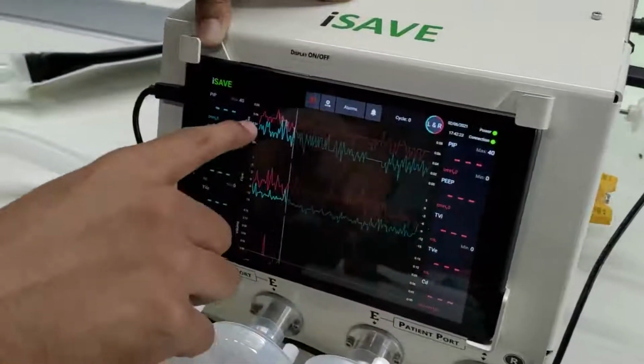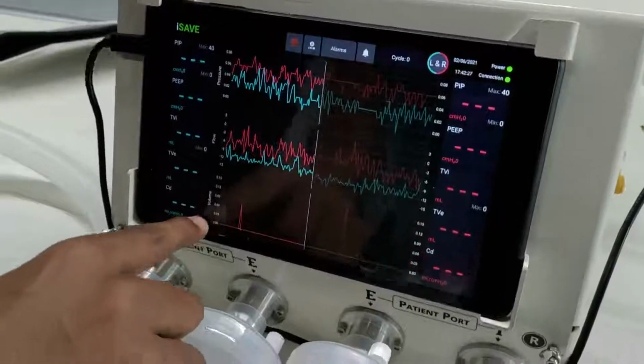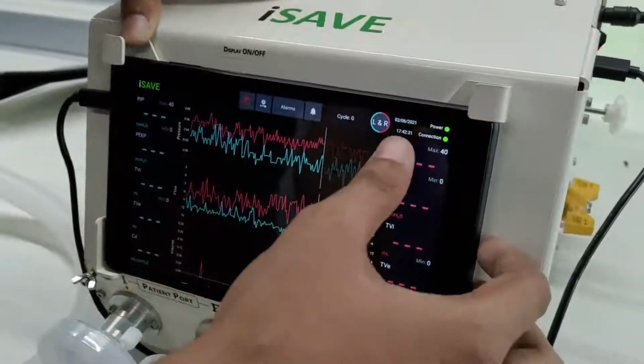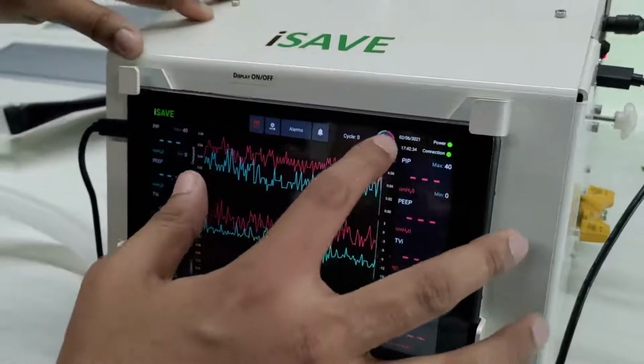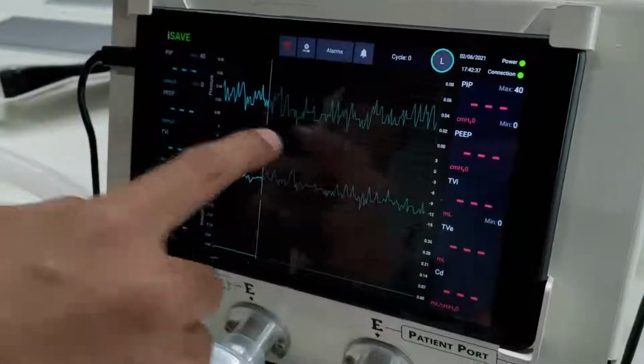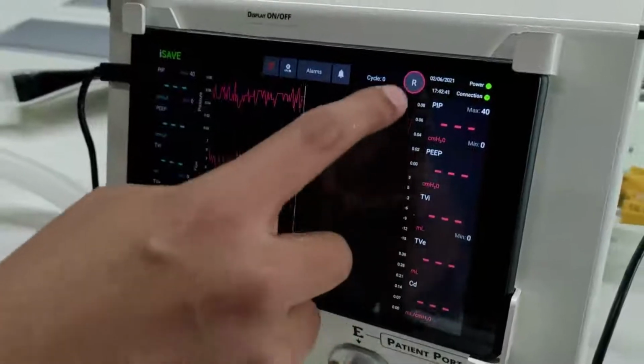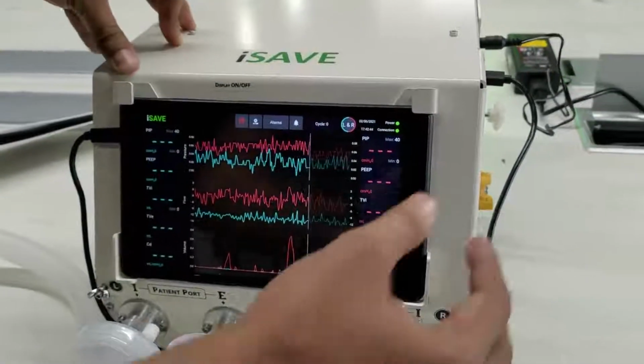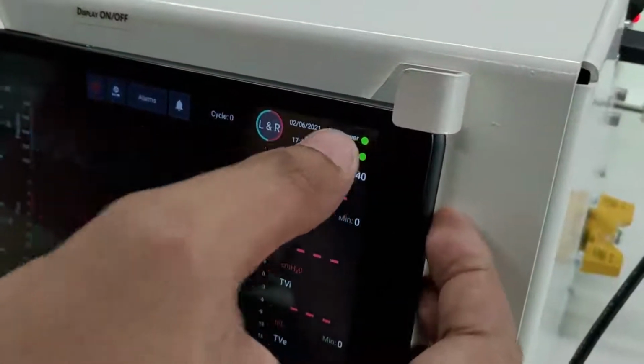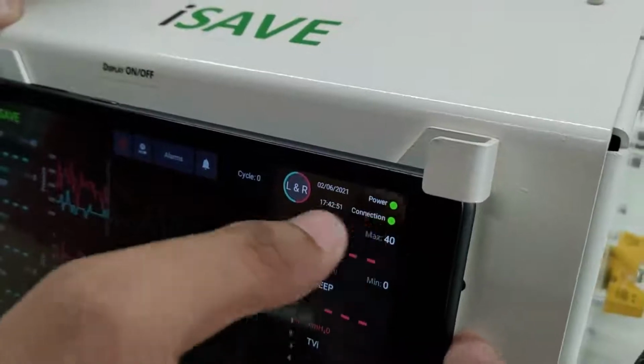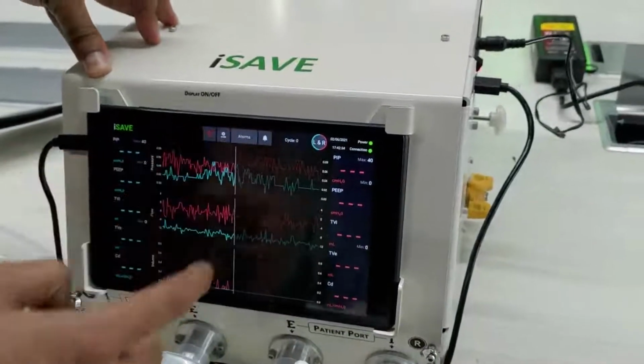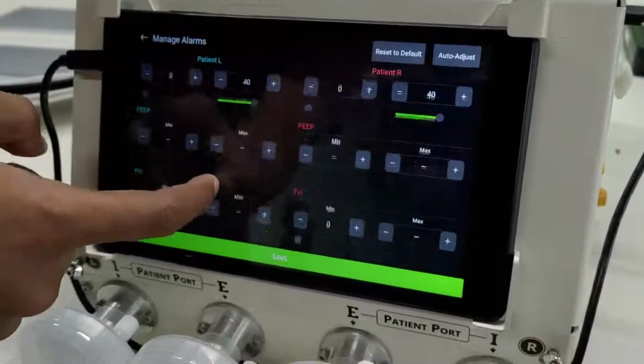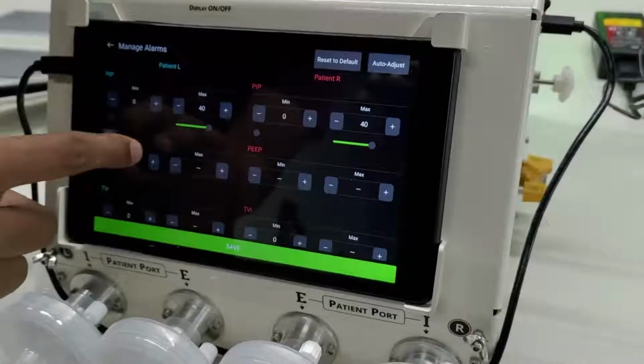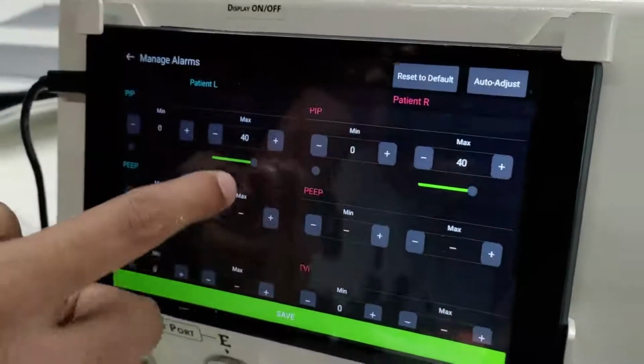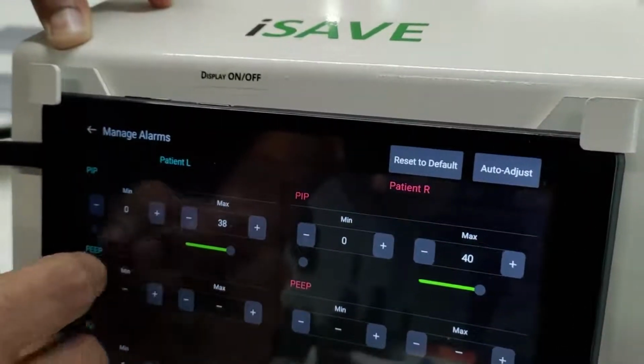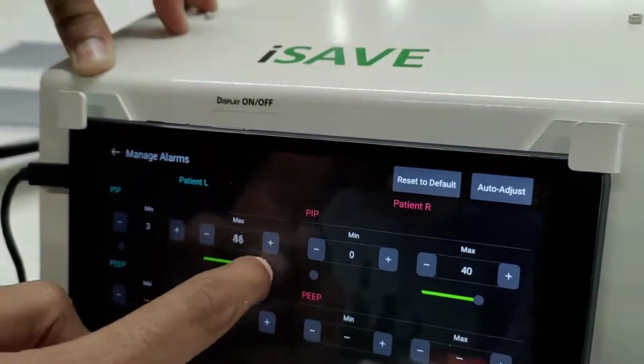Let me walk you through the other HMI features. We have the pressure, flow, and volume displayed here. If you want to switch through and see just one patient's graphs, you can click this circle over here. This is for the left patient, this is for the right patient, and this is for both patients. You need to make sure that your power is on so that the tablet will not lose power and the connection is present. We can also set the alarms here. We have an alarm screen, so we can set our min and max for PIP, PEEP, and tidal volume. We can set that using these plus or minus keys, or we can use a slider to adjust these values.